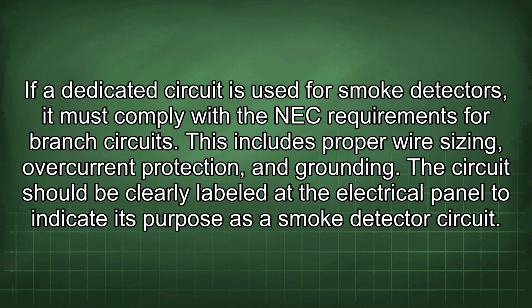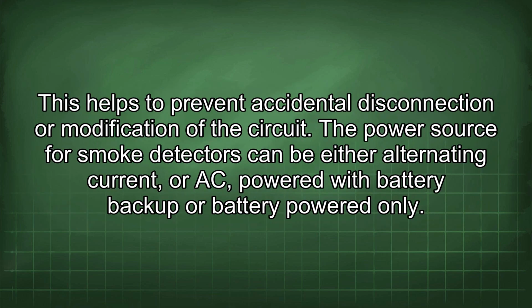If a dedicated circuit is used for smoke detectors, it must comply with the NEC requirements for branch circuits. This includes proper wire sizing, overcurrent protection, and grounding. The circuit should be clearly labeled at the electrical panel to indicate its purpose as a smoke detector circuit. This helps to prevent accidental disconnection or modification of the circuit.